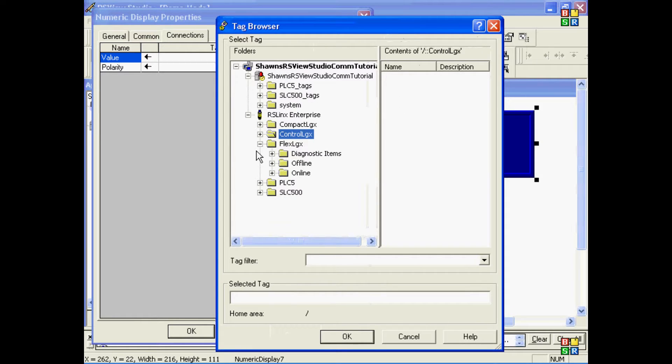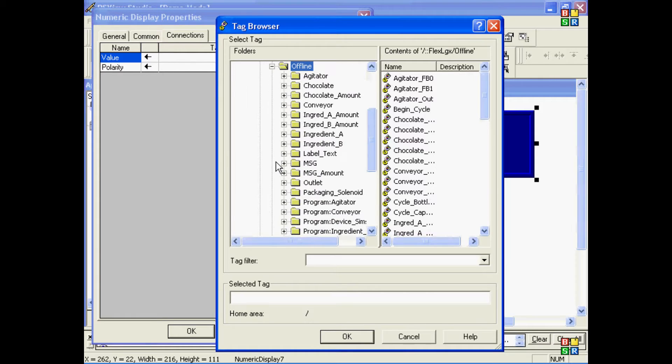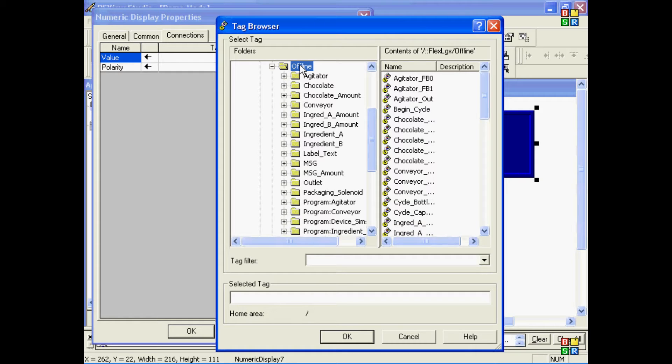Now, we actually don't have it connected, so I'll choose the Offline Folder. One thing to note about going to Offline Tag Browsing with Logix is that in version 3.1, this feature was very, very slow. In version 3.2, the version we're using right now, it works extremely well. But in version 4.0, you have to get a patch to get it to work as well as it did in 3.2.